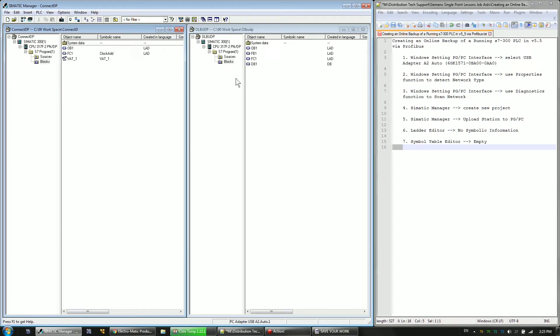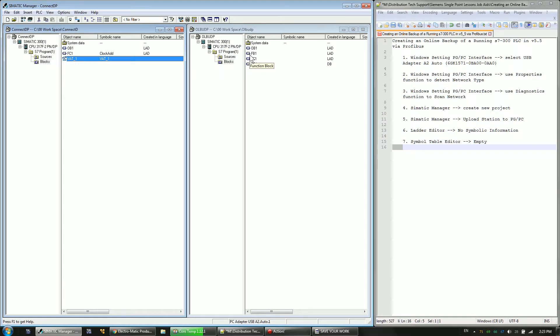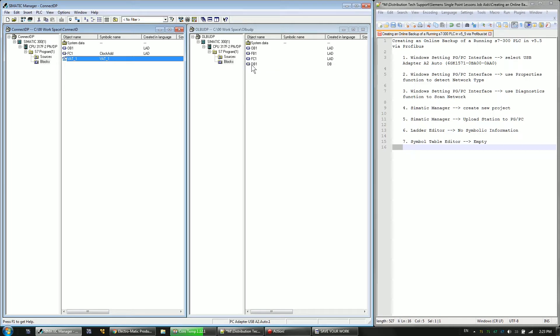Okay, so as you can see here, the online backup project is not showing the VAT that the standard project does. It actually is showing an FB. That FB is there from an old program. So that's actually still on the processor. It was never fully cleared out. And the DB is associated with that FB. It's not running. So it's got some garbage on there that was in the processor from before.